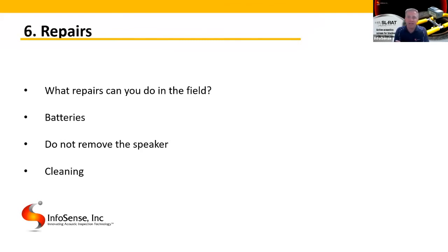The only repair that can be performed on the SL-RAT outside of our factory service center is to replace the main batteries. Do not remove the speaker. The speaker again is factory calibrated to each specific device, and they are not interchangeable. This is why most repairs can't be done in the field. The two units need to be calibrated and programmed to operate as a matched pair. That programming and all of our testing needs to be done in our shop.